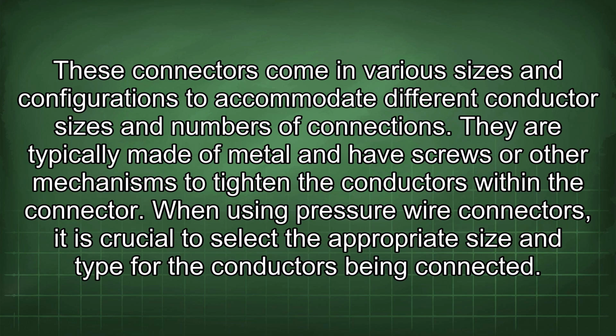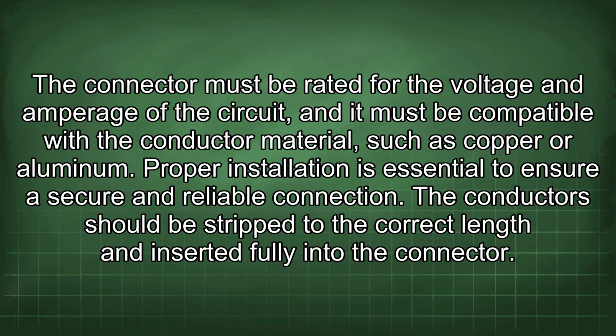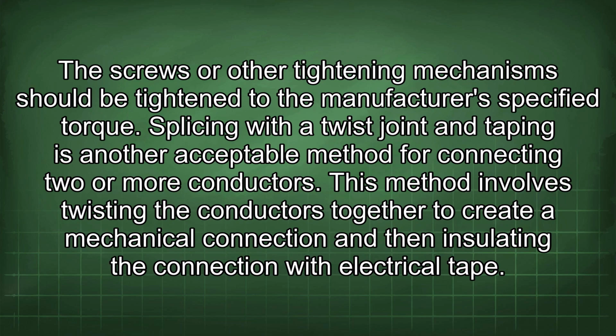When using pressure wire connectors, it is crucial to select the appropriate size and type for the conductors being connected. The connector must be rated for the voltage and amperage of the circuit, and it must be compatible with the conductor material such as copper or aluminum. Proper installation is essential to ensure a secure and reliable connection. The conductors should be stripped to the correct length and inserted fully into the connector. The screws or other tightening mechanisms should be tightened to the manufacturer's specified torque.